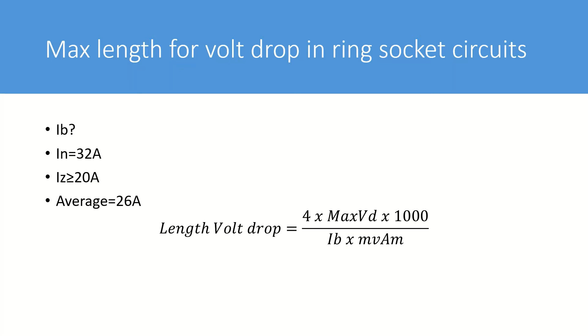One solution to this is by taking the average of 32 amps the rating of the protective device and 20 amps and we get a figure of 26 amps. So this can be used in place of the design current in this equation here.